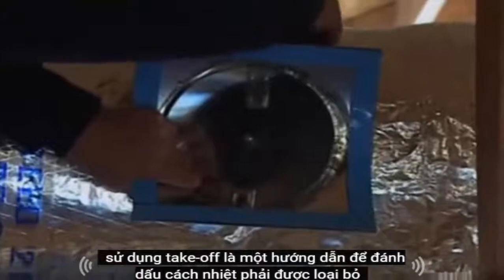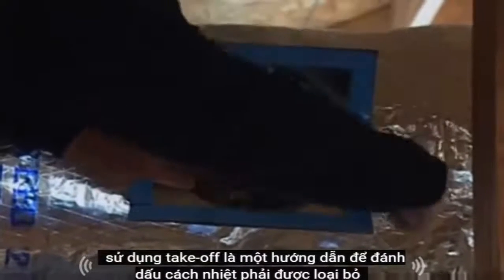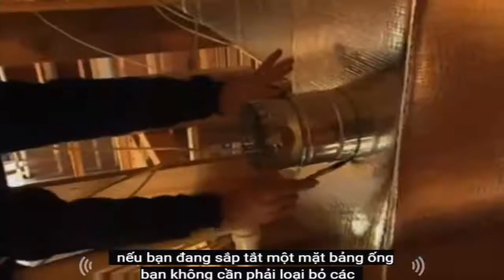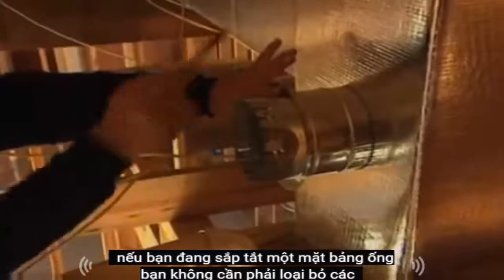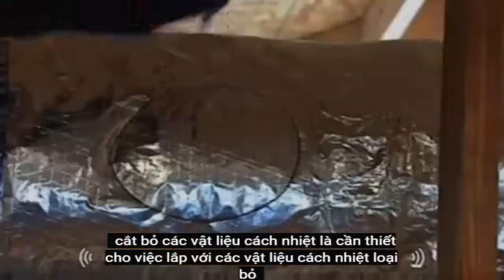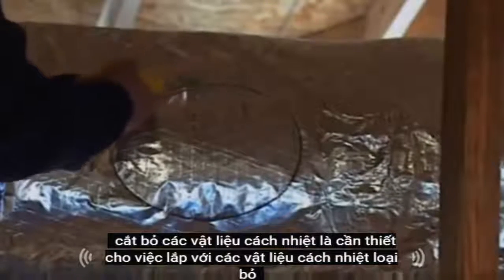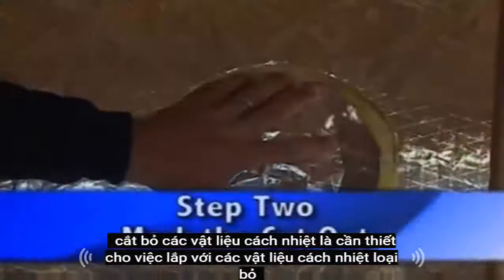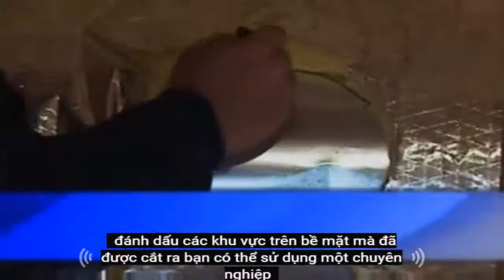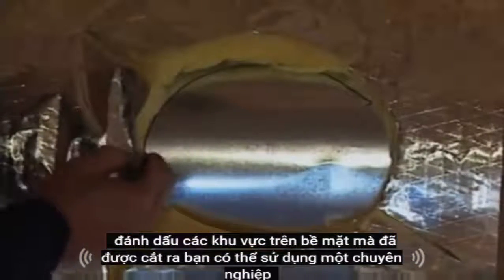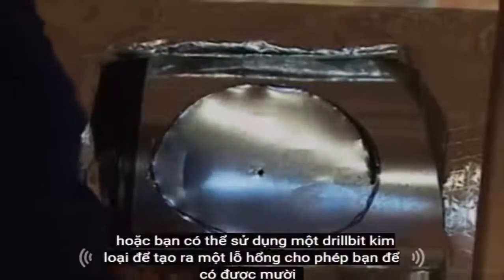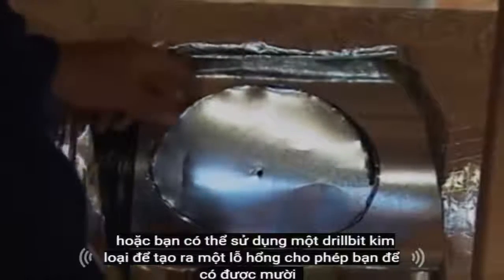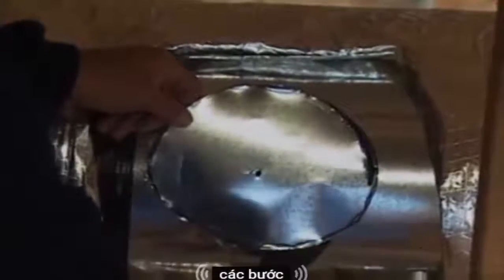Use the takeoff as a guide to mark the insulation that must be removed. If you're coming off a duct board surface, you do not need to remove the insulation. Cut away the insulation as needed for the fitting. With the insulation removed, mark the area on the surface that has to be cut out. You could use a professional hole cutter, or you could use a metal drill bit to create a hole that allows you to get tin snips into the pipe.